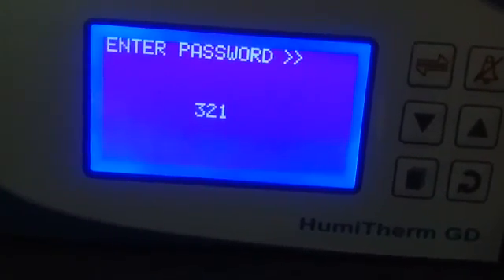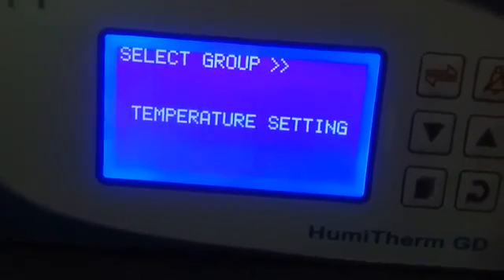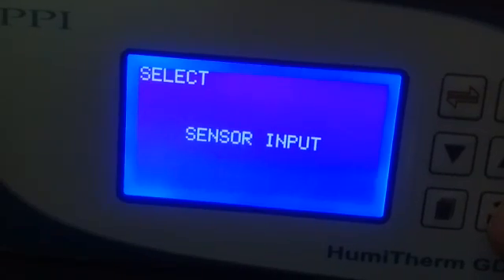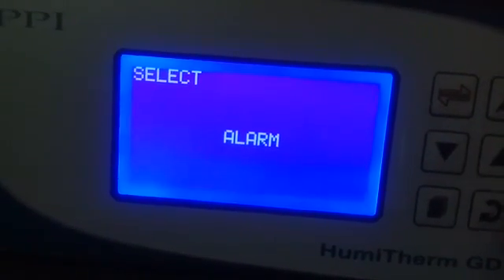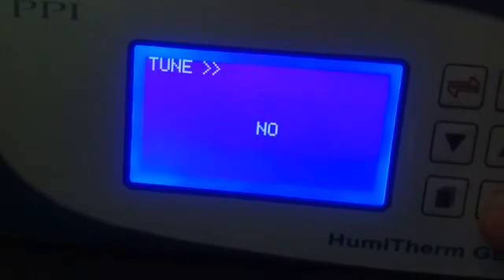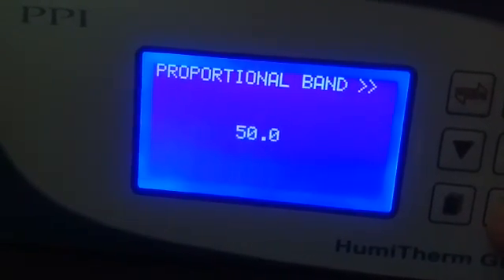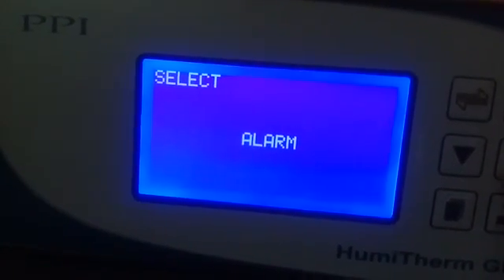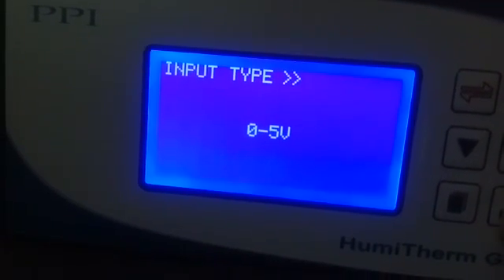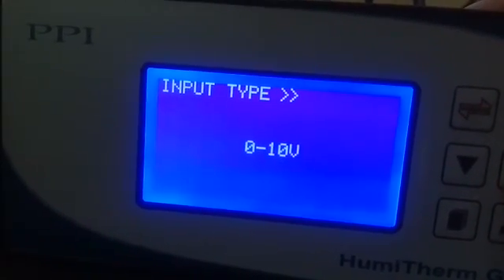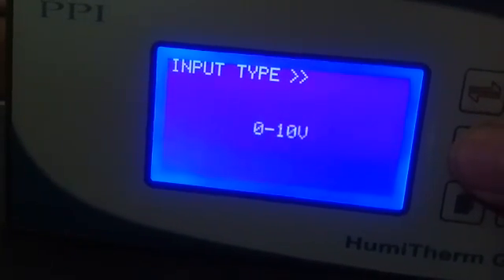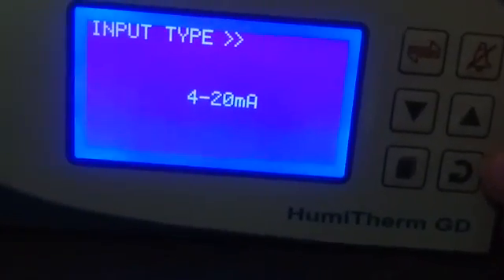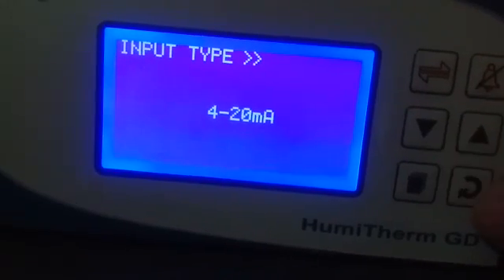The password is 3-2-1. Here you have temperature settings: alarm control, sensor input — you can select alarm if required — control tune, set point low limit, set point high limit, proportional, integral, derivative, cycle time. Now for humidity, you can set sensor input: 0-5 volt, 0-10 volt, 1-5, 4-20, 0-20. Here you can select 4-20 as you are using a humidity transmitter — this is to be selected.